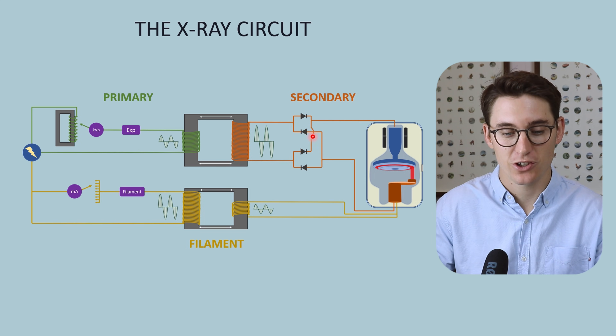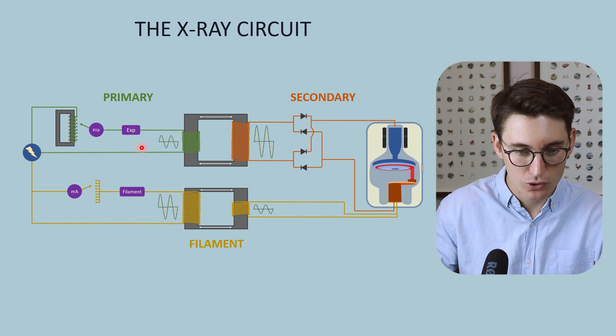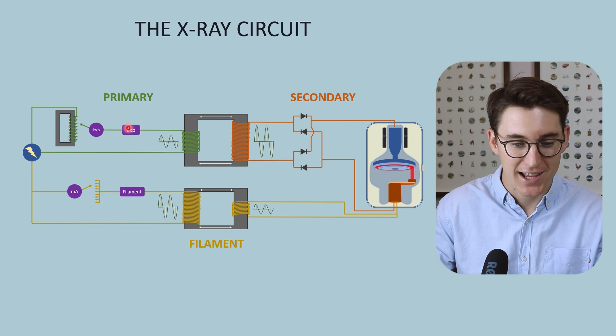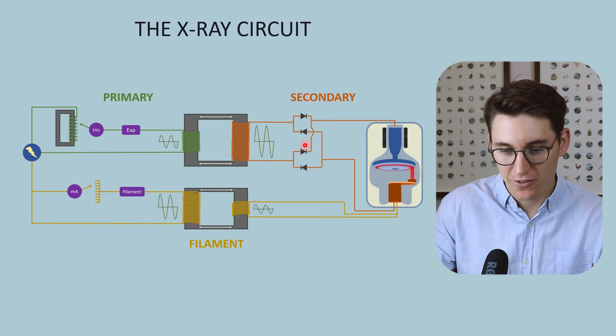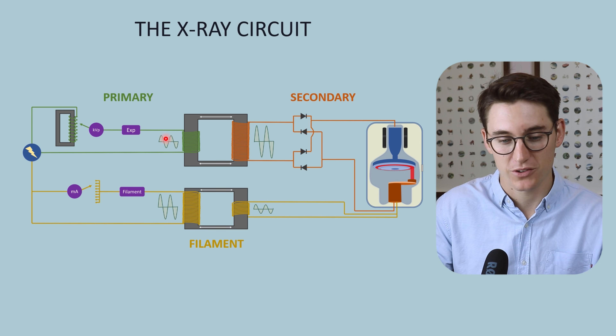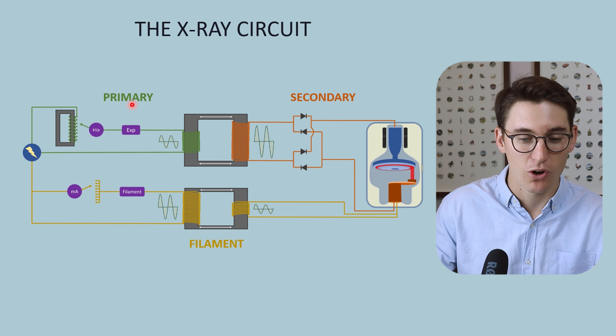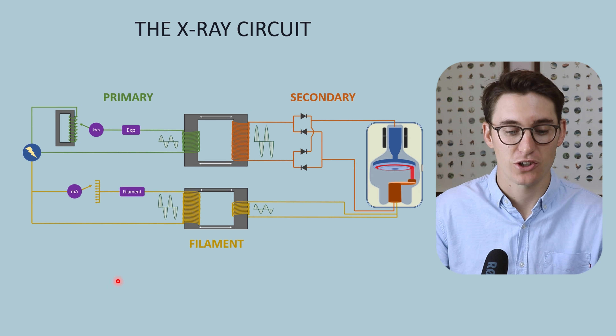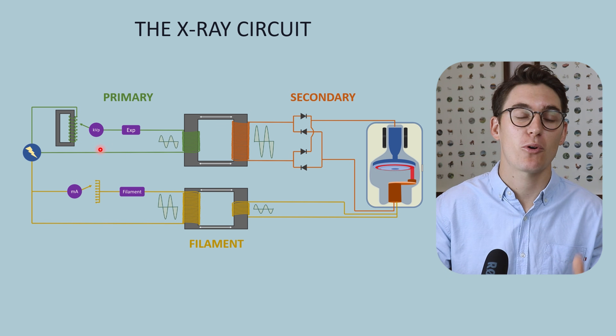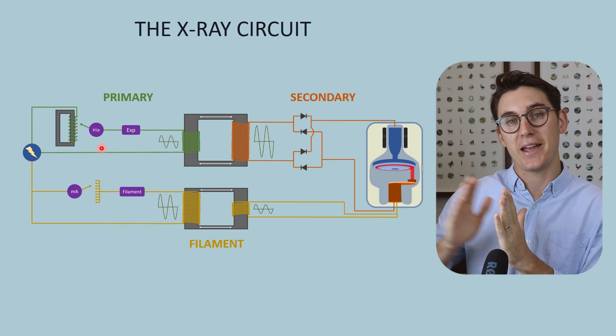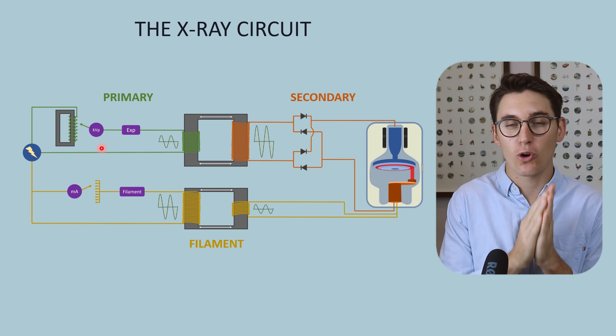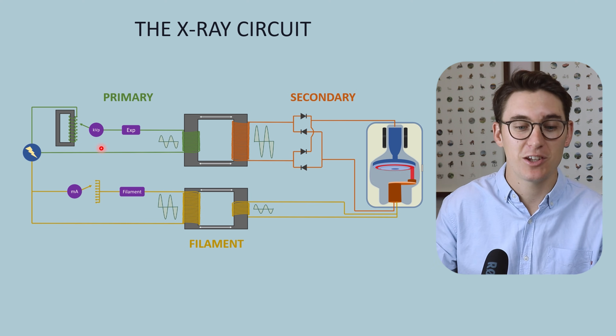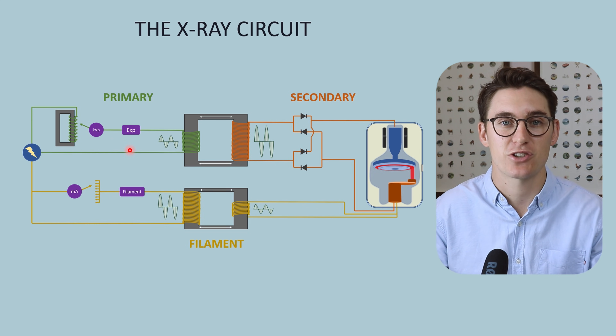Before moving to the secondary circuit, note that the controls we change — selecting kVp and exposure time — are in the low-voltage part of the circuit. We never manipulate anything within the high-voltage circuit, which is a key safety measure. We are only ever exposed to the low-voltage parts: the primary and filament circuits. These components come up repeatedly in exams because they have a major effect on the x-ray spectrum, particularly how changes in kVp and exposure time manipulate that spectrum.